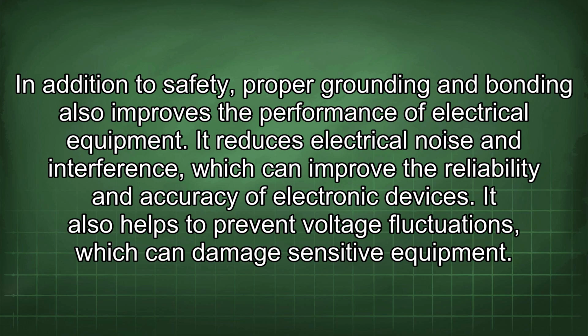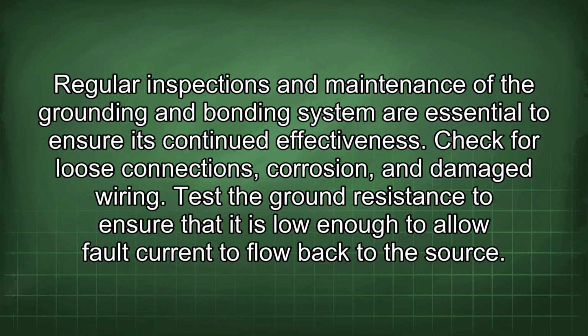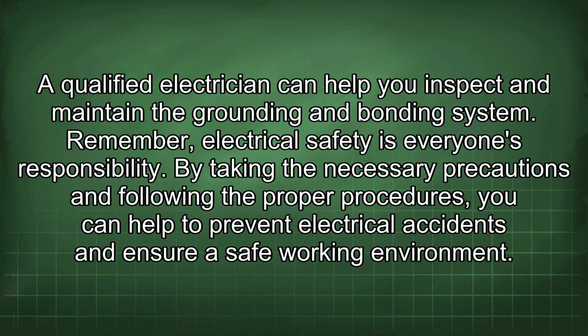It reduces electrical noise and interference, which can improve the reliability and accuracy of electronic devices. It also helps to prevent voltage fluctuations, which can damage sensitive equipment. Regular inspections and maintenance of the grounding and bonding system are essential to ensure its continued effectiveness. Check for loose connections, corrosion, and damaged wiring. Test the ground resistance to ensure that it is low enough to allow fault current to flow back to the source. A qualified electrician can help you inspect and maintain the grounding and bonding system.